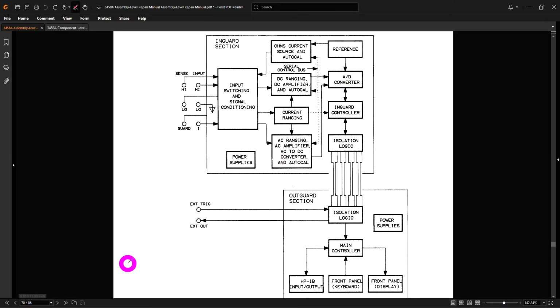All right, now time to dig into the actual circuit architecture. And luckily, there's a lot of information available that we can dig into and see if we can understand the problem. So this is the overall block diagram of this instrument. This is obviously looking at it from a very high level, but we should be able to deduce some information. So here's the inputs coming into the unit. And then we have something called an input switching and signal conditioning. This entire board, which is the A2 board, I believe, is floating, and therefore it is isolated from the rest of the instrument because of the sensitivity of everything that's on here.